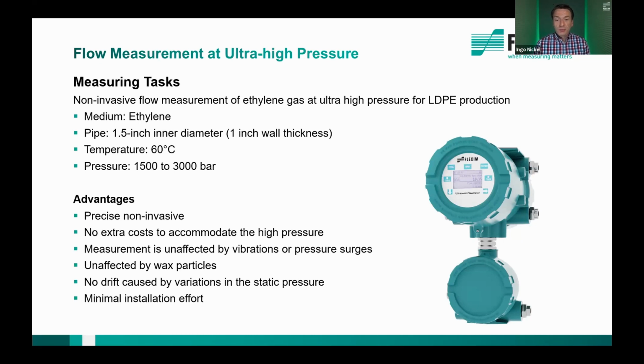But if you're using a non-invasive approach, no pipes must be opened or removed. We have a minimal installation effort, and this results in no additional cost to accommodate this required high pressure rating if you're using a clamp-on flow meter. Furthermore, the measurement of the ultrasonic clamp-on flow meters is completely unaffected by vibration or wax particles. Wax particles can have a significant impact on other flow measurement technology, and a drift of measurement values by variation of the static pressure cannot be observed with the clamp-on flow meter solution from us.